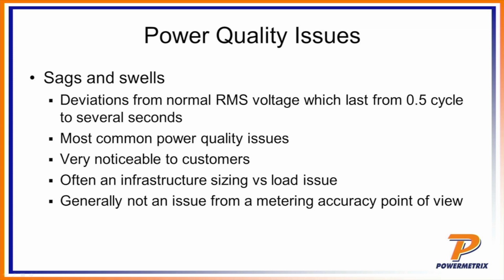For the meterman, the important thing to note is that sags and swells typically are not an issue in terms of metering accuracy. That's because the meters are designed to accommodate a wide range of voltages. Even if it's designed to be nominally a 120 volt meter, the ANSI C12 standard, which dictates how a meter is designed and built, will accommodate anywhere from half the nameplate voltage to twice the nameplate voltage and still not damage the meter or really affect the metering accuracy.